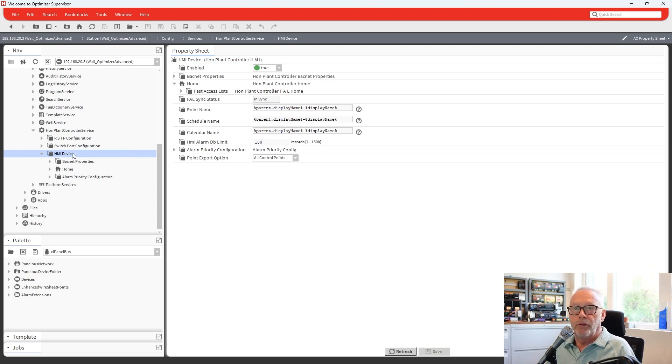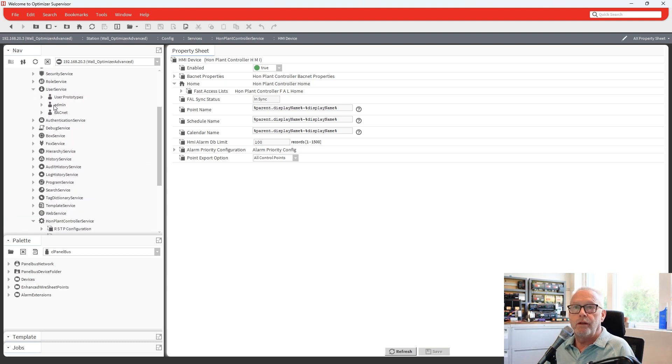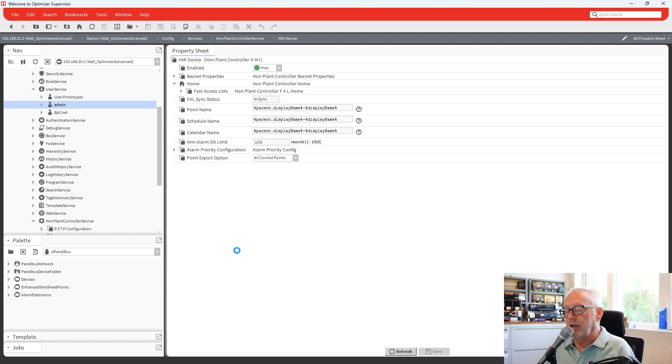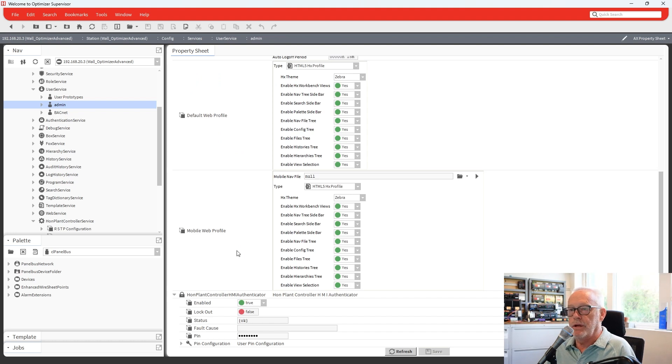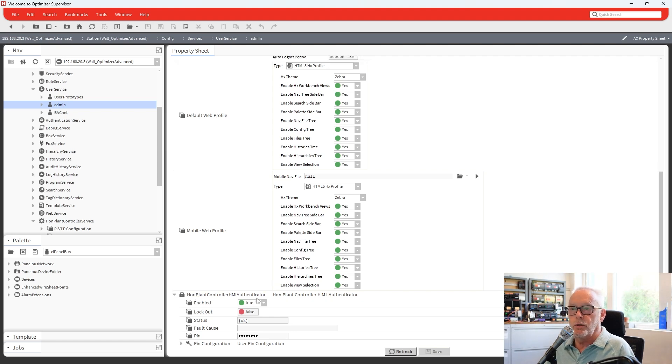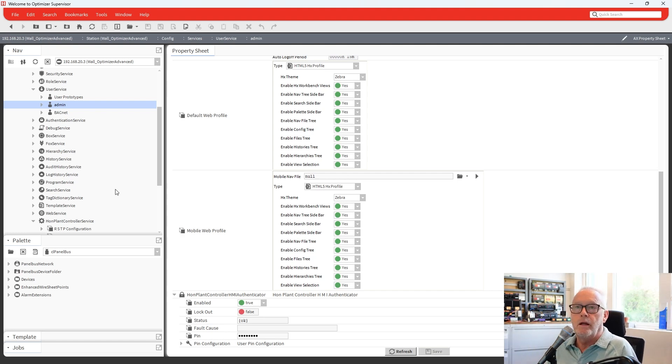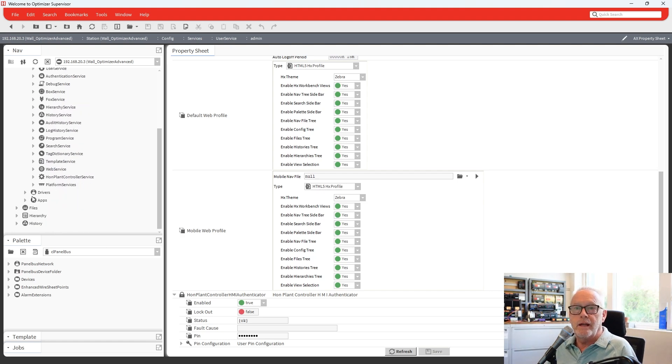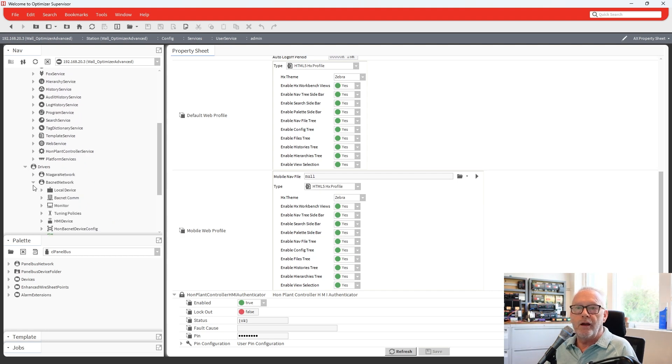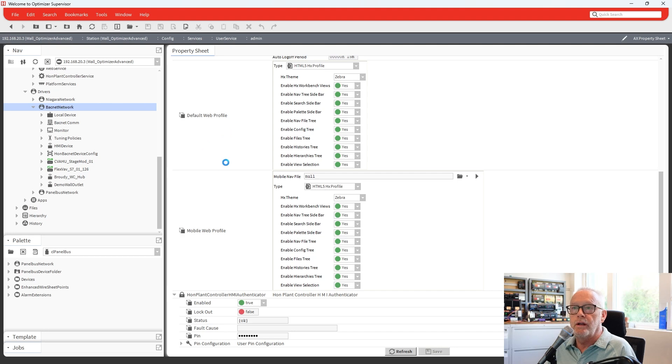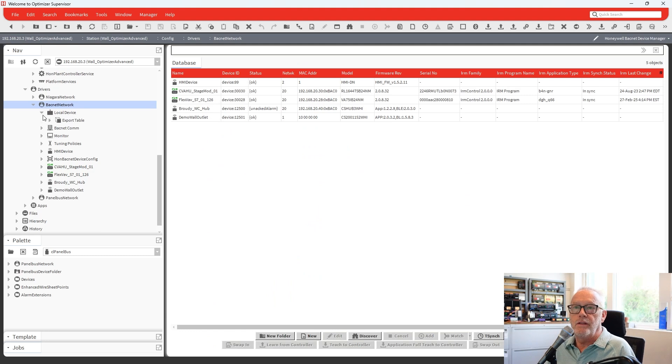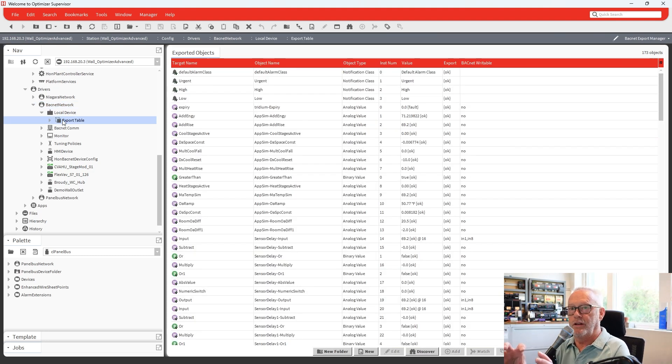A couple things you have when you do use the HMI: your user service will have at the very bottom a PIN number that you would set up. So each user of the HMI would get a PIN number based on the Niagara user. And then there's a section down here at the bottom, HON plant controller authenticator. So that's something where you would put the PIN number in for your password to get into the HMI and work with it. The other part is when you built that, it actually goes in the BACnet network and becomes a device on the BACnet network. And all the points that get populated on the HMI are located in the export table of the BACnet network. So all that's contained within the BACnet network.